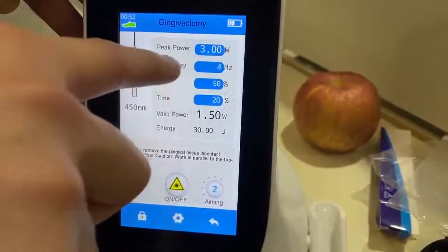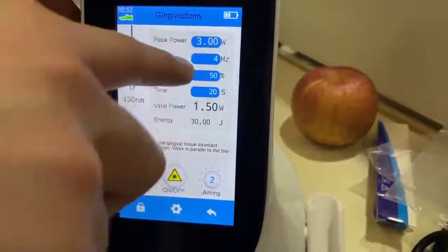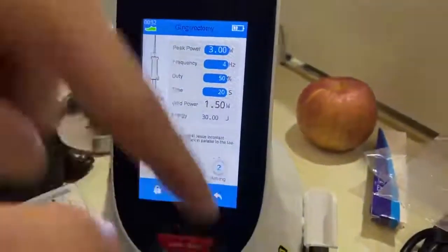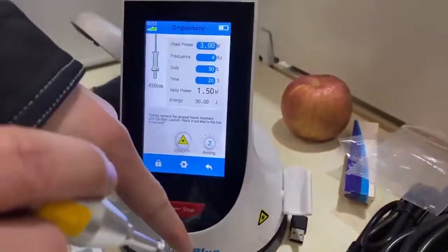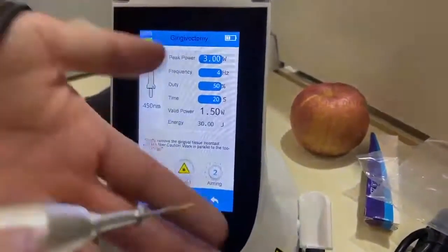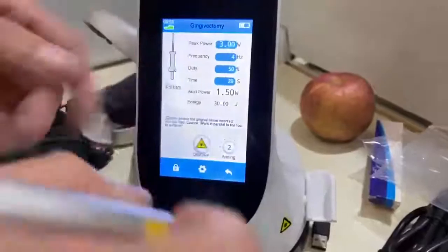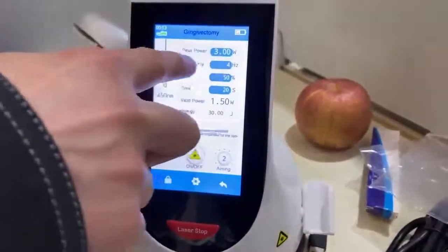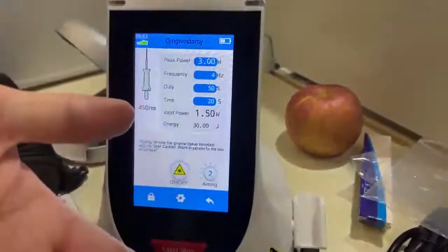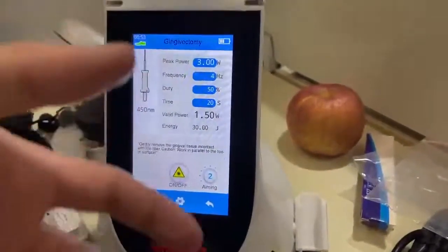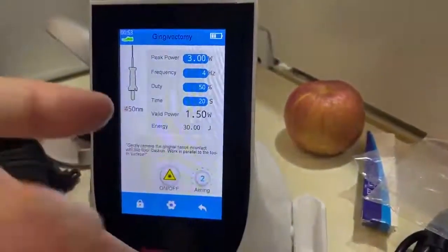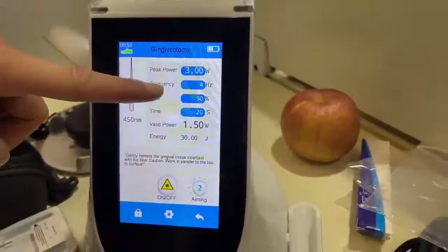Also, usually if we increase the frequency, the laser will penetrate less. If you reduce the frequency, the laser will penetrate more into the soft tissue. So that's the difference. For example, if you are going to cut the soft tissue, you don't need the laser to penetrate more, so you just increase the frequency or even use the continuous mode. But if you want to use the laser, for example, for sterilization or for therapy, you can reduce the frequency. Then the laser can go deep into the soft tissue. So that's how to set the frequency.